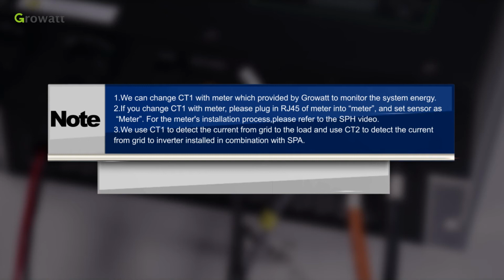2. If you change CT1 with a meter, please plug the RJ45 for the meter into the meter and set the sensor as meter. For the meter's installation process, please refer to the SPH video. 3. We use CT1 to detect the current from grid to the load and use CT2 to detect the current from grid to the inverter installed in combination with SPA.